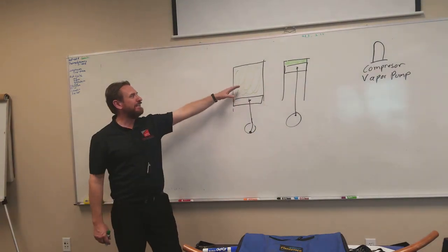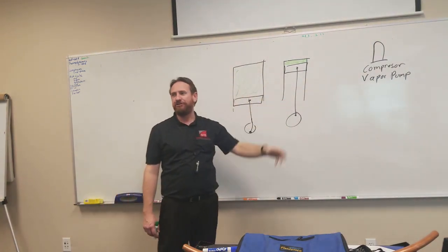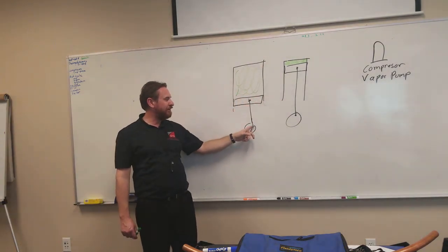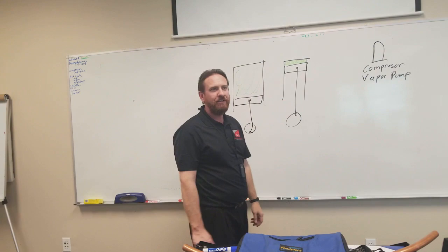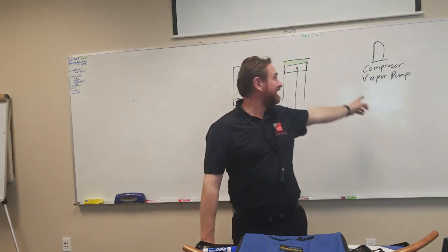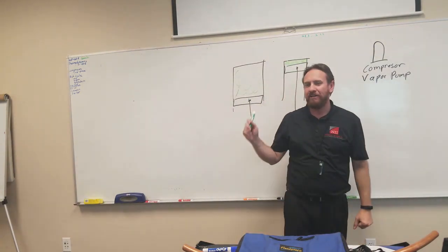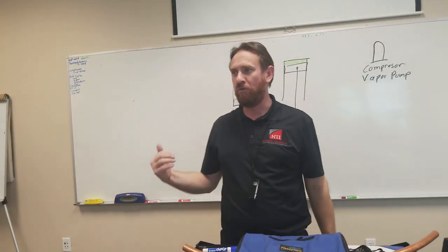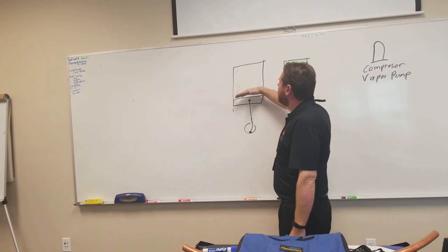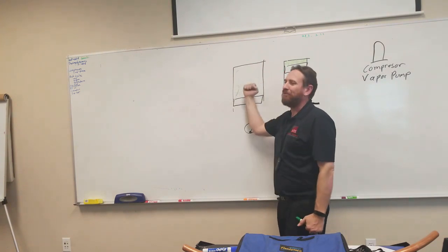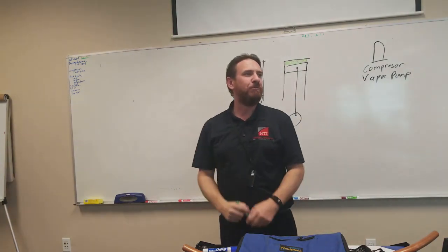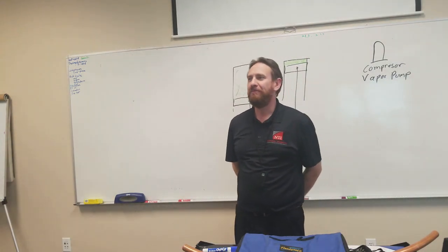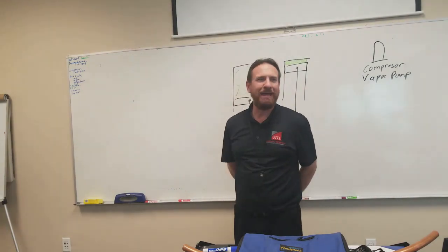If we get liquid in a compressor, it will destroy it. Something will break. The valves will break, the piston will break, the connecting rod will break. So we do not ever want to get liquid in here because something is going to break. If you've ever seen or heard about a car being hydro-locked, it gets water in it. If you get water in it, it fills that cylinder and you try to compress that liquid and something will break. Hopefully it just shuts down, but usually it means something's breaking, bending, giving, bad stuff's happening.